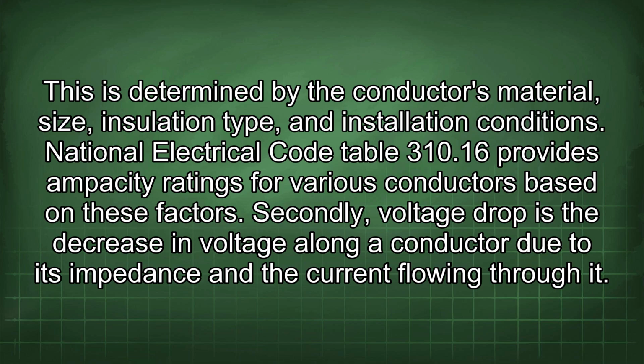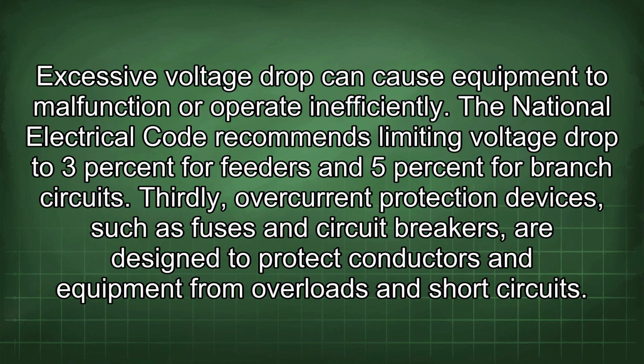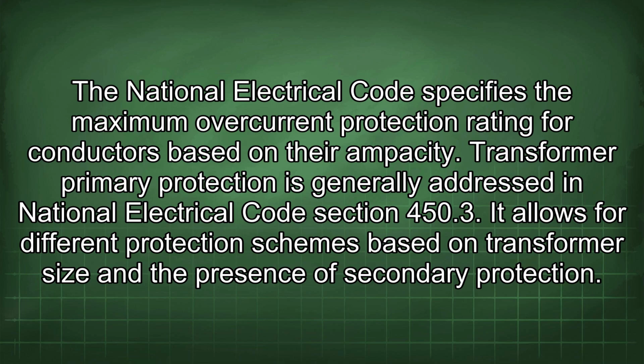Secondly, voltage drop is the decrease in voltage along a conductor due to its impedance and the current flowing through it. Excessive voltage drop can cause equipment to malfunction or operate inefficiently. The National Electrical Code recommends limiting voltage drop to 3% for feeders and 5% for branch circuits. Thirdly, overcurrent protection devices, such as fuses and circuit breakers, are designed to protect conductors and equipment from overloads and short circuits. The National Electrical Code specifies the maximum overcurrent protection rating for conductors based on their ampacity.